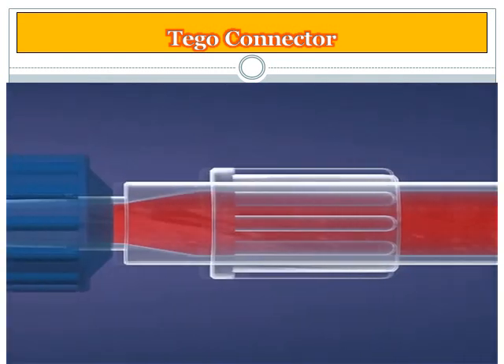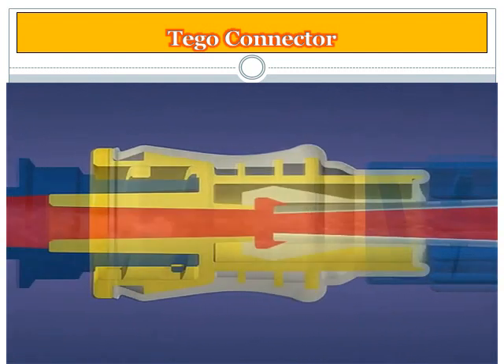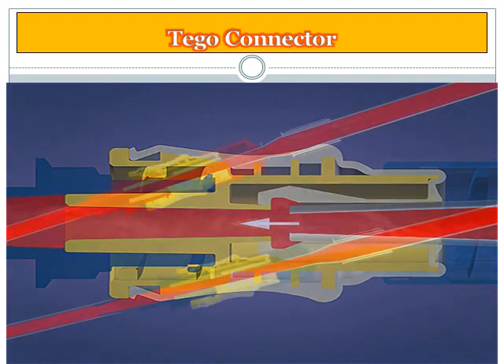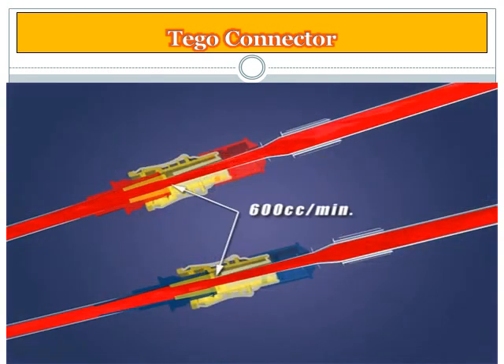The Tego has a unique straight-through, unobstructed fluid path which is critical for maintaining the integrity of the blood while still providing a flow rate of more than 600 cc per minute.